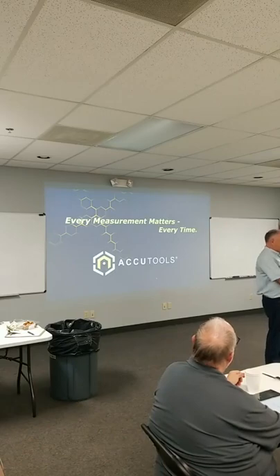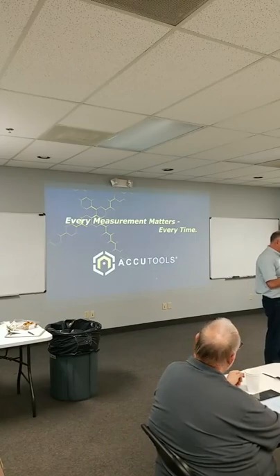There's a fitting on the top here, this is called the centering ring. So you can't tighten it beyond the centering ring. As soon as it's touching here, it's sealed. If I drew a vacuum on this hose right now, I don't even really need a clamp on it. The only reason you need a clamp is it's annoying when the fitting falls off and there's no vacuum. So these are standard clamps you'll see in industrial process vacuum.